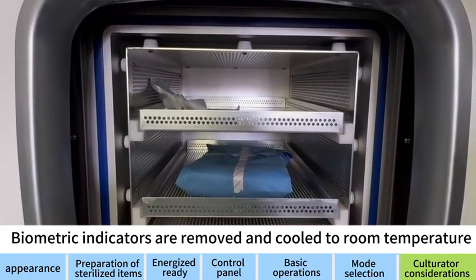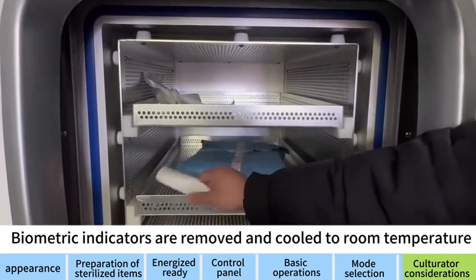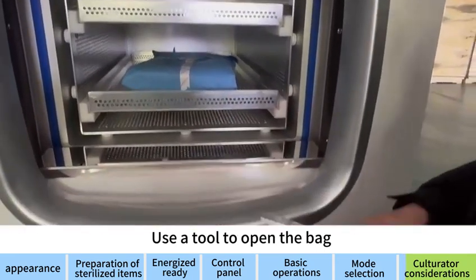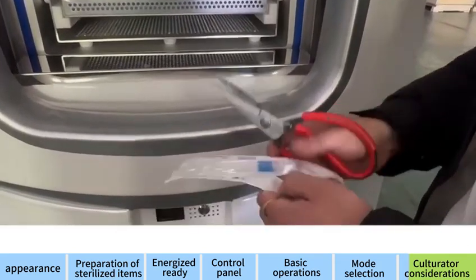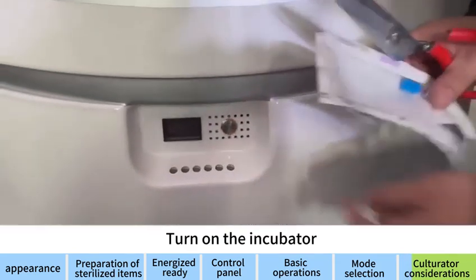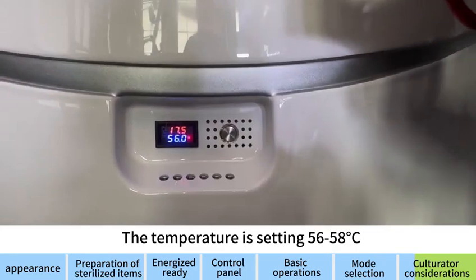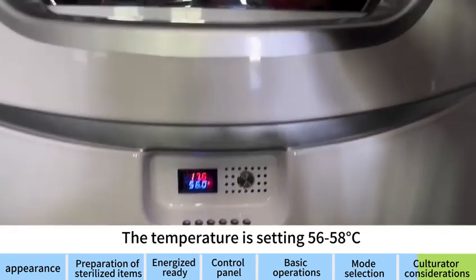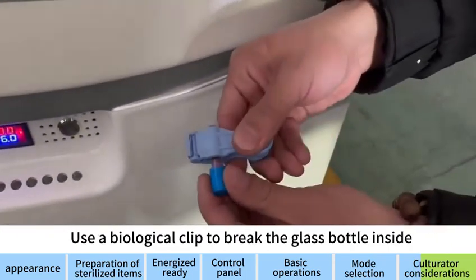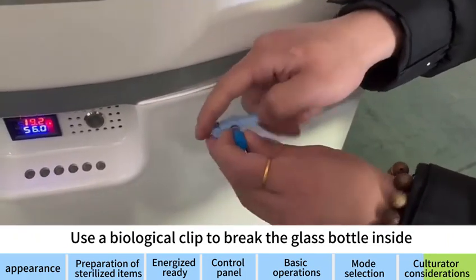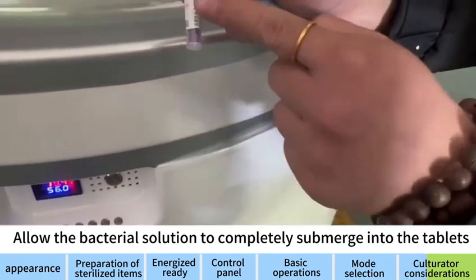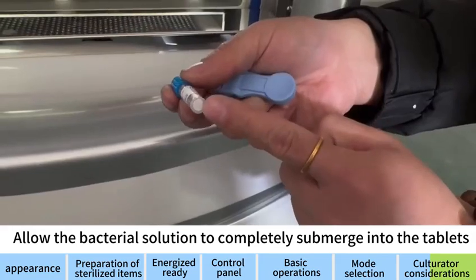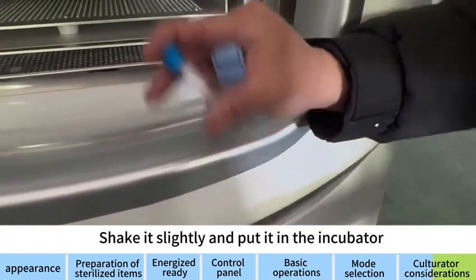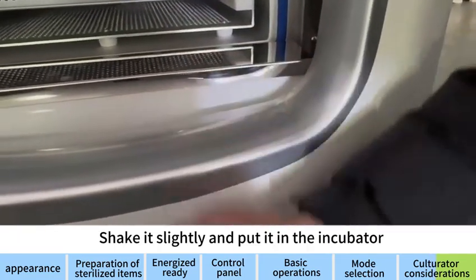Biological indicators are removed and cooled to room temperature. Use a tool to open the bag. Turn on the incubator. The temperature is set at 56 to 58 degrees Celsius. Use a biological clip to break the glass bottle inside. Allow the bacterial solution to completely submerge the tablets. Shake it slightly and put it in the incubator.